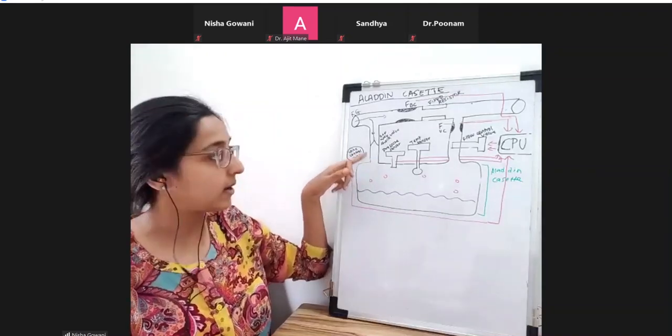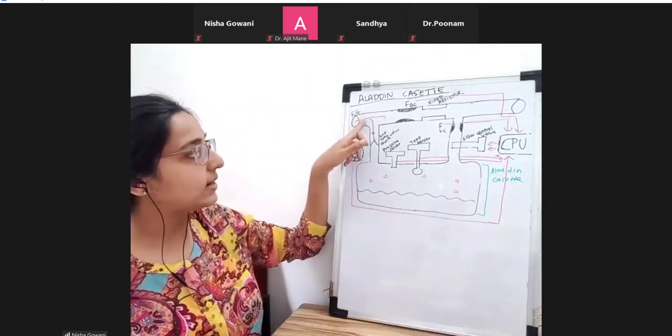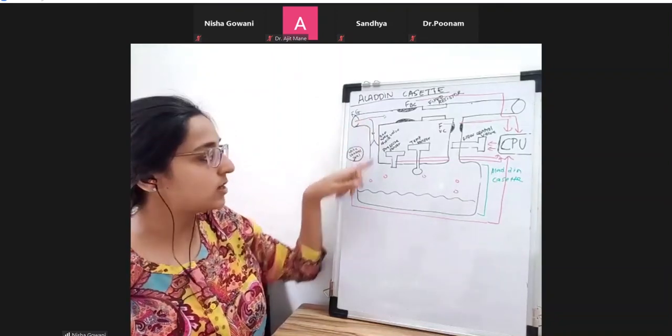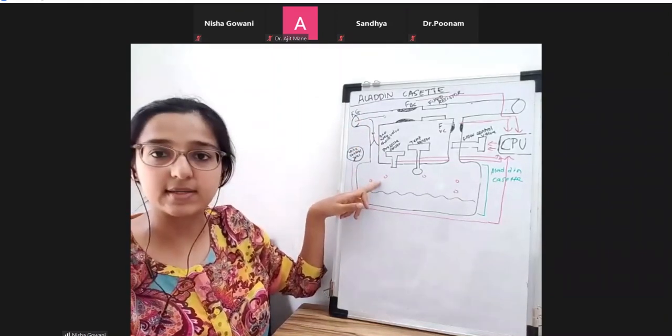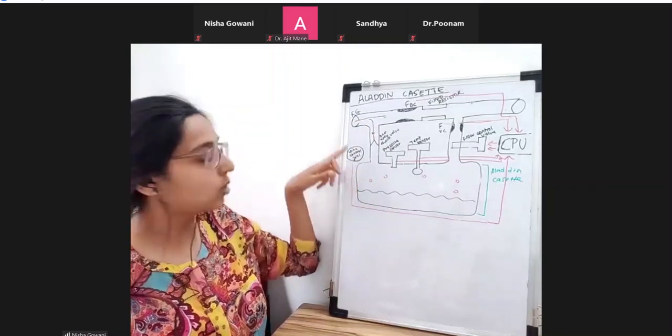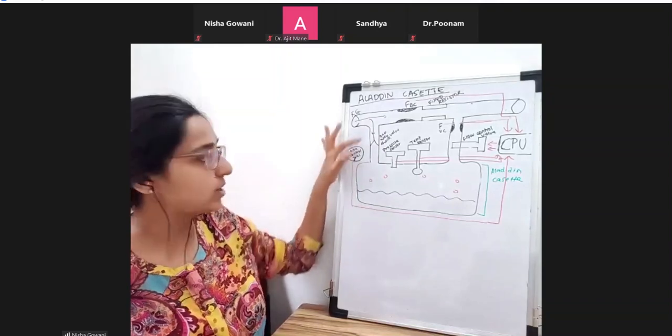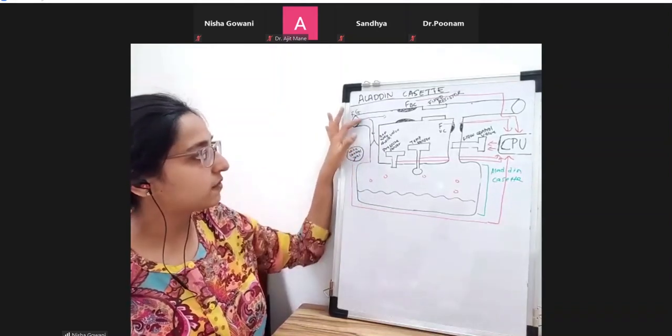Next, what will happen? Now whatever fresh gas is incoming will not be able to enter into the vaporizing chamber. So now the one-way check valve was closed. Fresh gas cannot enter in. There is no movement of gas over here. So fresh gas can't come in.